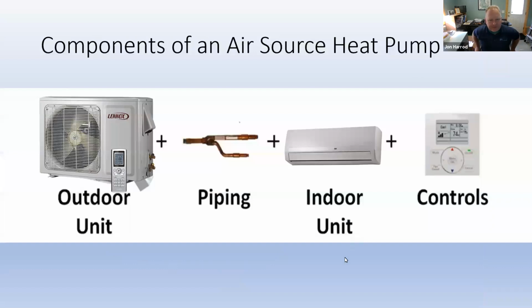The basic components of the air source heat pump are the outdoor unit, which contains the compressor, most of the controls, and the outdoor heat exchanger—in wintertime the evaporator, in summertime the condensing coil. That's connected to the indoor unit with piping that carries the refrigerant between the units. There's an indoor unit containing the indoor heat exchanger as well as a blower fan, and each system has controls that allow occupants to adjust it for their comfort needs.